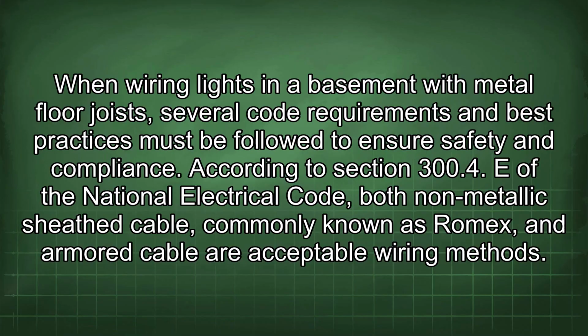When wiring lights in a basement with metal floor joists, several code requirements and best practices must be followed to ensure safety and compliance. According to Section 300.4 E of the National Electrical Code, both non-metallic sheathed cable, commonly known as Romex, and armored cable are acceptable wiring methods.